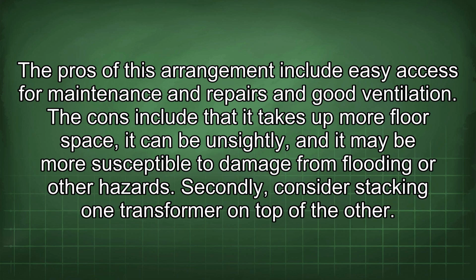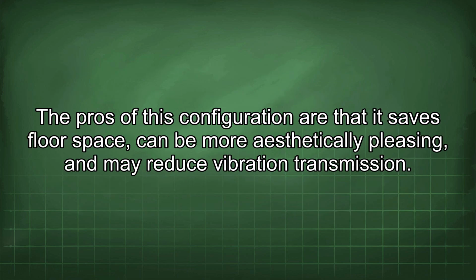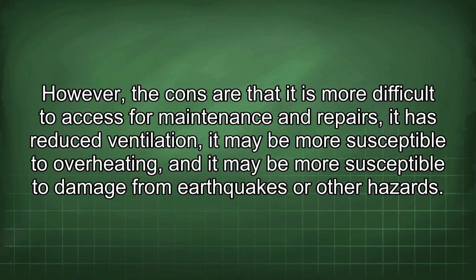Secondly, consider stacking one transformer on top of the other. The pros of this configuration are that it saves floor space, can be more aesthetically pleasing, and may reduce vibration transmission. However, the cons are that it is more difficult to access for maintenance and repairs, it has reduced ventilation, it may be more susceptible to overheating, and it may be more susceptible to damage from earthquakes or other hazards.